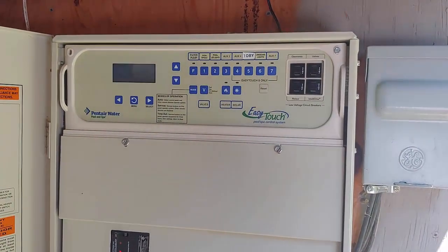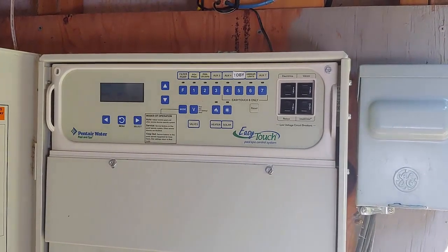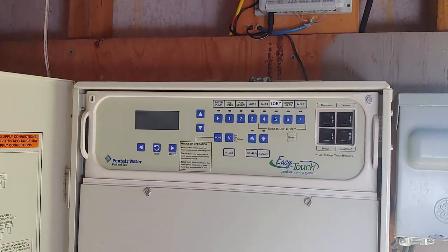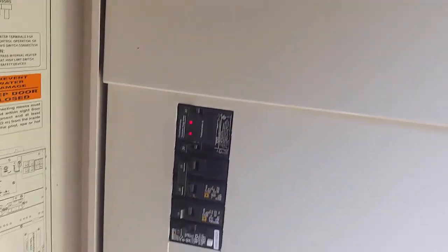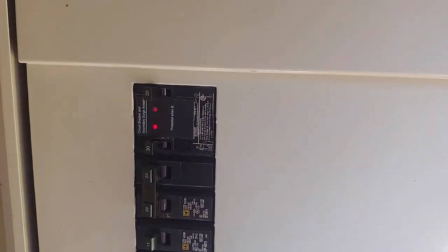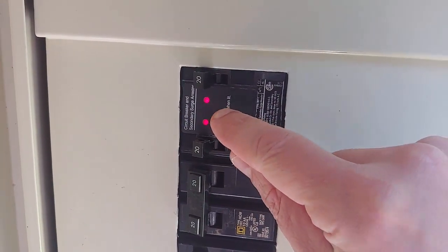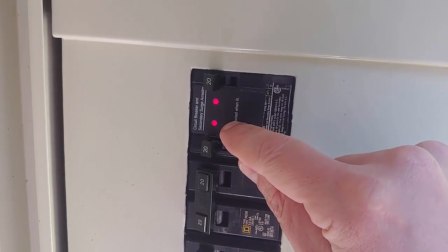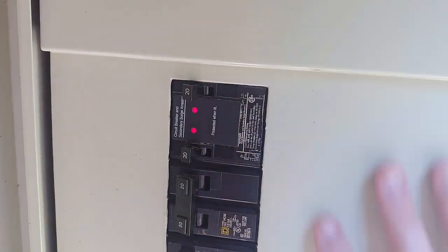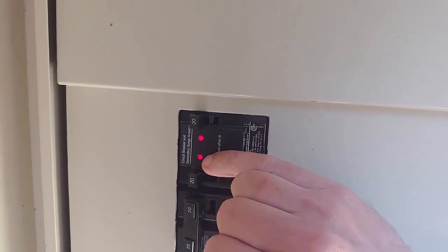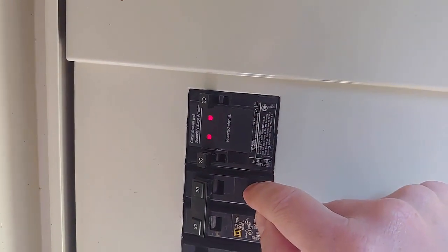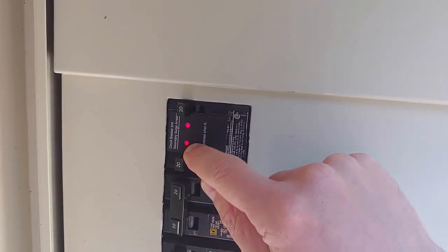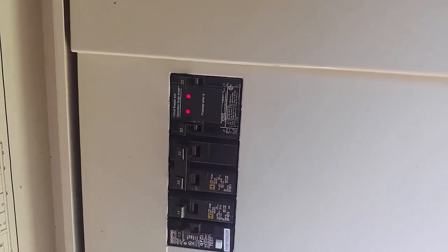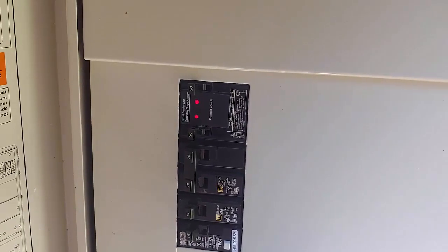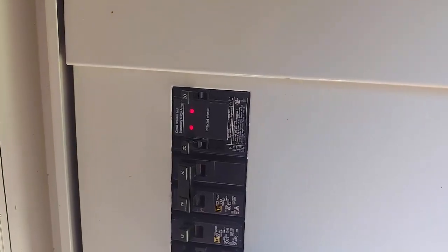Now in my house I have whole house surge protection, and in addition to that, I have whole house surge protection out here. You definitely want to do this with this expensive equipment. This is a whole house surge protection breaker, one of the easiest ways you can provide full protection for your Easytouch, on the high voltage side anyway. These red lights indicate, and you can get these breakers from different vendors, that active surge protection is happening for each leg. There are 2 legs in here, 120 and 120 make up the 240, or 110 makes up 220. So this is the high voltage side, low voltage side, as I said.